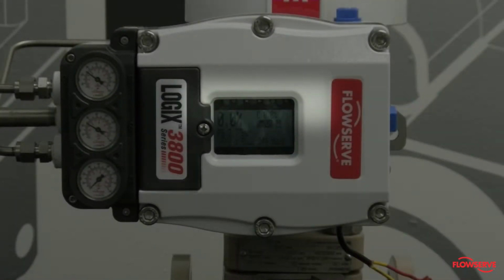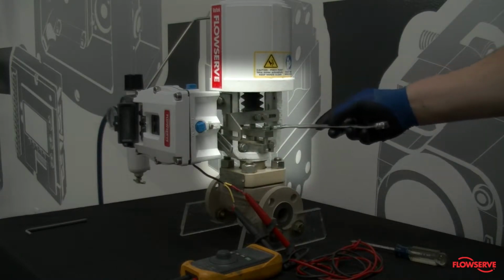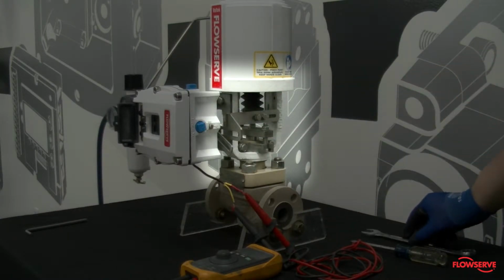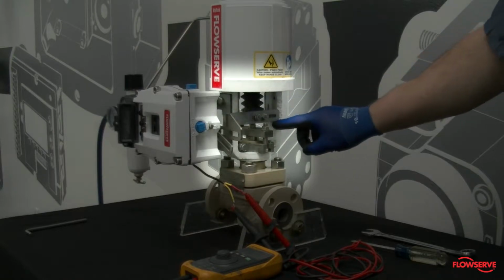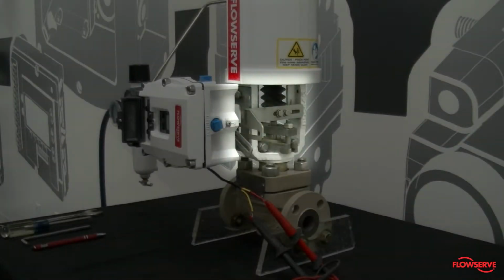Next, verify that the LEDs are blinking. This indicates that the positioner is correctly powered and ready for calibration. Now verify that there are no obstructions, including tools or fingers, in the area of the actuator and plug stem. This is a critical verification because the calibration will stroke the valve, moving the plug stem up and down.